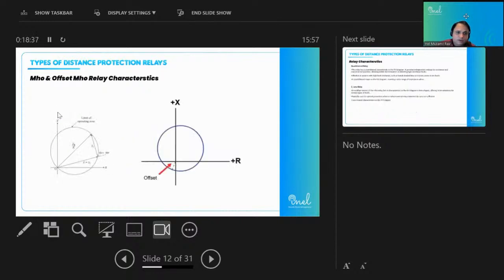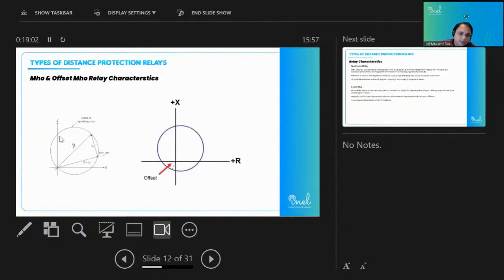So the MHO relay, let me show you this one. This is the MHO relay characteristic. This has a directional feature, like now it is starting from the origin of that plane. Now it is not seeing on the left side of this plane. Like this one was equally on the right side and equally on the left side, but this has that directional feature. It is only seeing in the forward direction of the line. And now due to this one, it has another feature, which is very much, I think, the beauty of this characteristic.